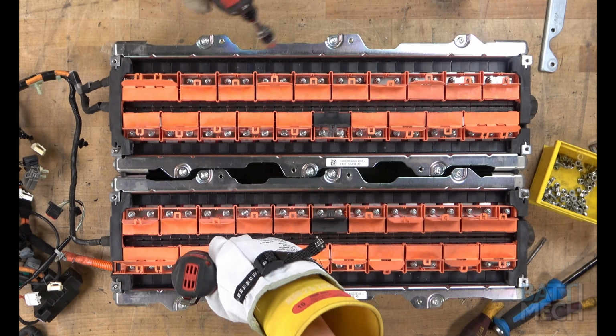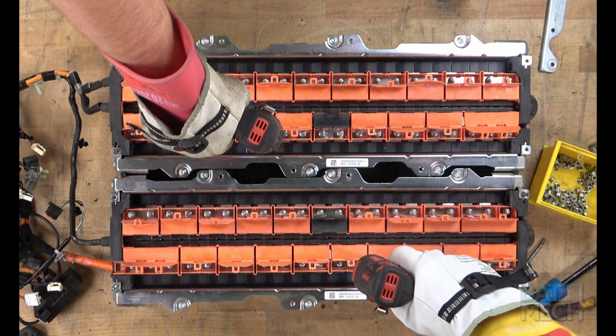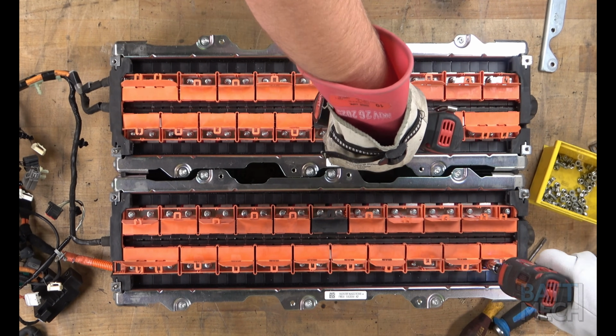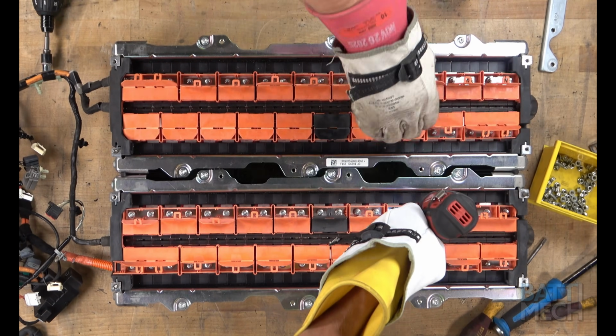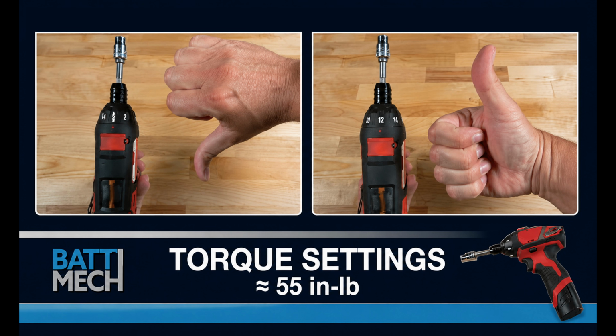After the nuts have been put into place, use the special socket included in your purchase from BattMech to lightly tighten the terminal nuts. Note: be sure your torque settings on your torque wrench are set to about 55 inch-pounds. If you don't follow these torque settings, you are likely to damage the terminals on the batteries and will void your warranty. Never use max drill settings and never use an impact wrench.